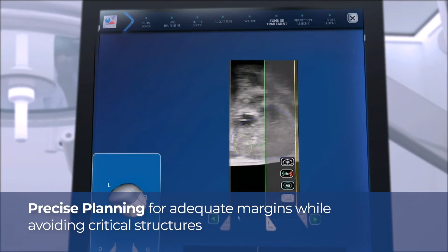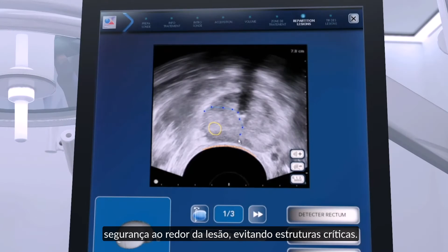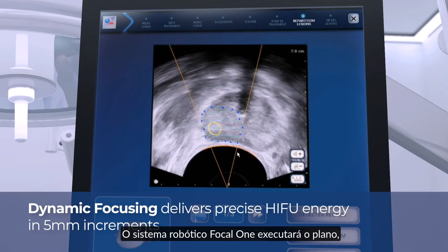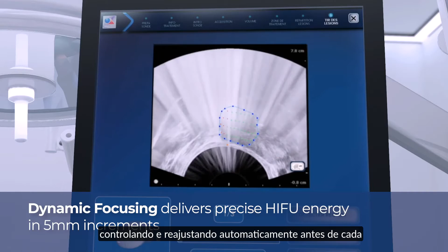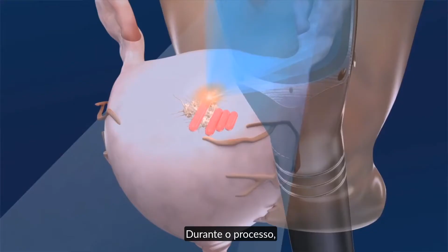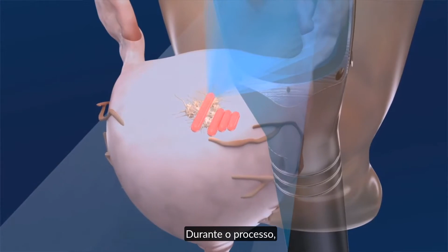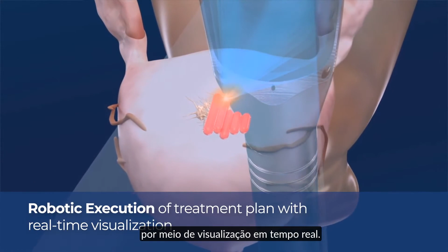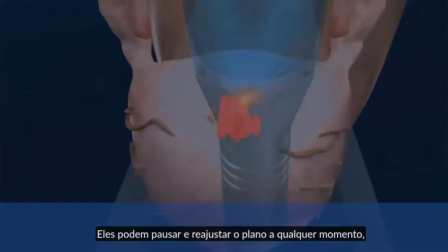The urologist then precisely defines the upper and lower limits of the treatment zone. The computerized system creates virtual slices every 1.7 millimeters to cover the whole ablation area. For each individual slice, the operator shapes the contour of the target to provide a safety margin around the lesion while avoiding critical structures. The Focal One robotic system will execute the plan, controlling and readjusting automatically before each individual pulse of HIFU energy. During the process, the urologist maintains control and monitors the ablation through real-time visualization. They can pause and readjust the plan at any time.